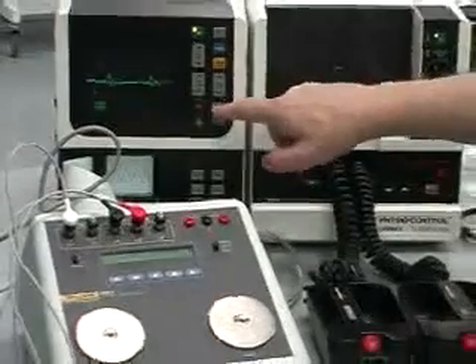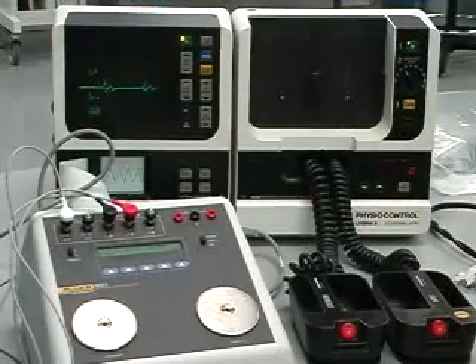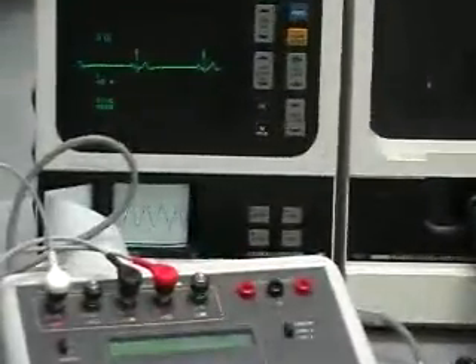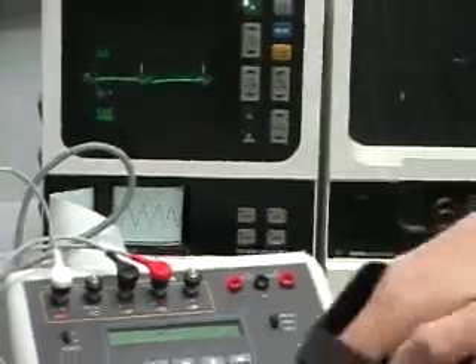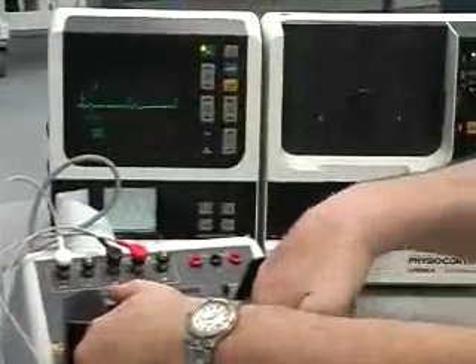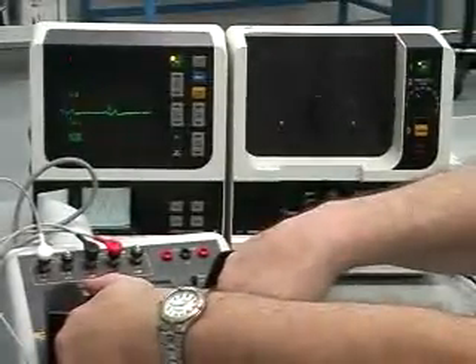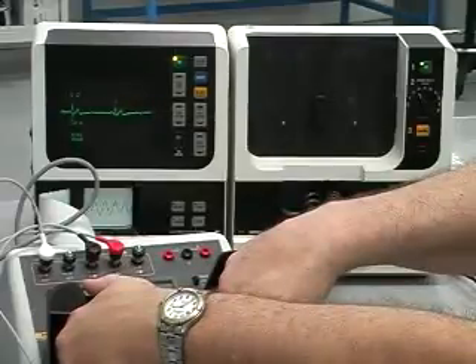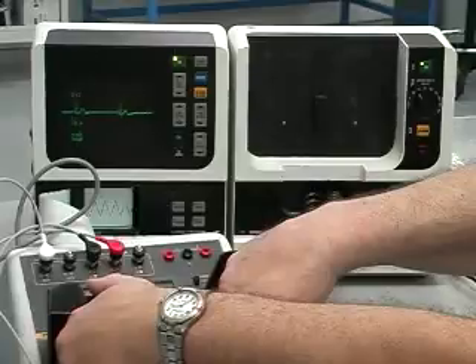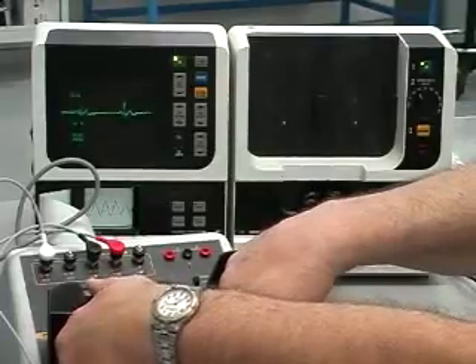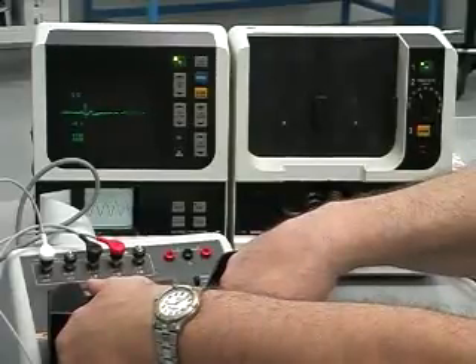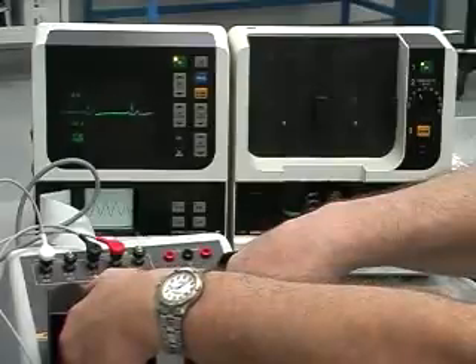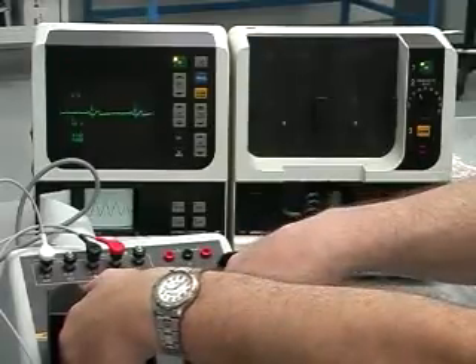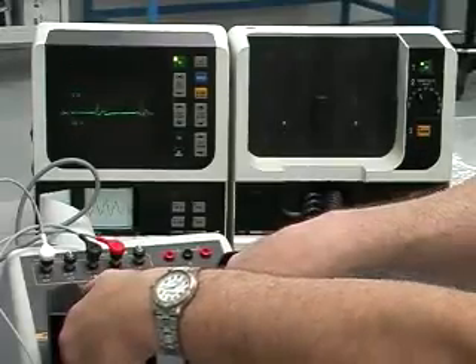So right now, we're running a very slow ECG. Okay. And you can hear when the ECG comes through, exactly, and the mark is on the leading edge of the pulse. Now what's going to happen, I'm just going to put these here and first charge it up just to 30 joules. Normally if you discharge the defib, it's going to do it immediately. But in this case, I'm just going to wait until that ECG waveform goes by, push the buttons, and then it won't discharge until the next ECG waveform comes through. So I'll wait for one to go through. Now I've got the buttons pushed. It doesn't discharge until that ECG comes through.